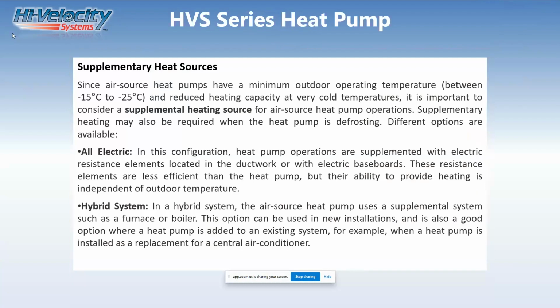Well, heat pumps. I want to talk about that because we do offer a heat pump. And the information I'm going to fill in here is, since an air source heat pump has a minimum outdoor operating temperature between minus 15 and minus 25, reducing the heating capacity at very cold temperatures, it's important to consider a supplementary heat source. For air source heat pump operation, supplementary means something extra that you might need because it doesn't become efficient for the heat pump to run.